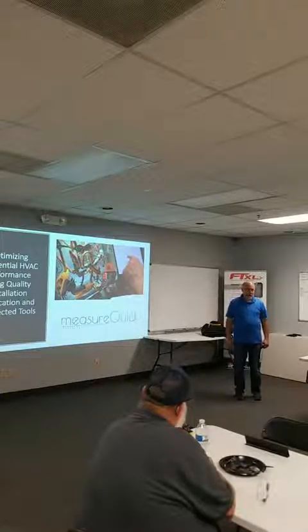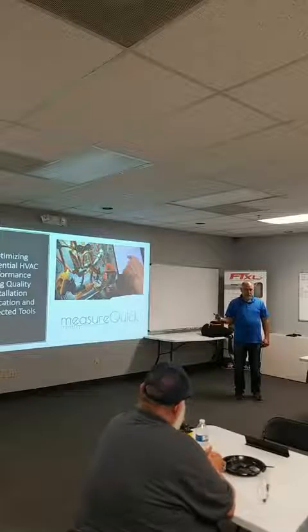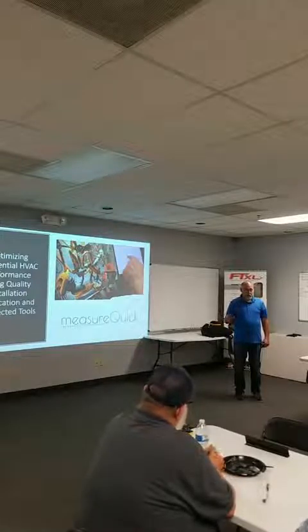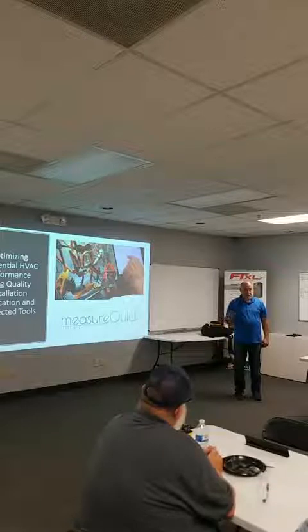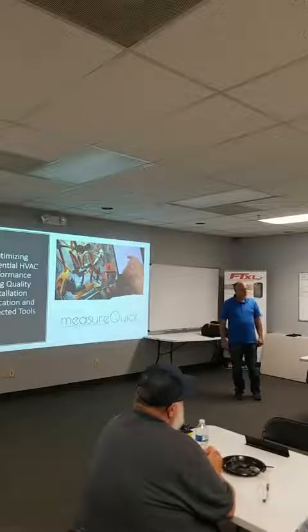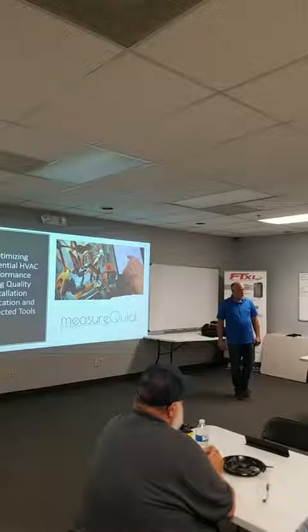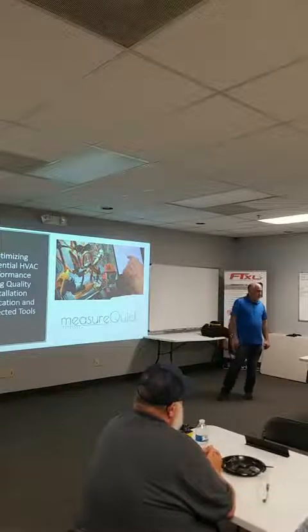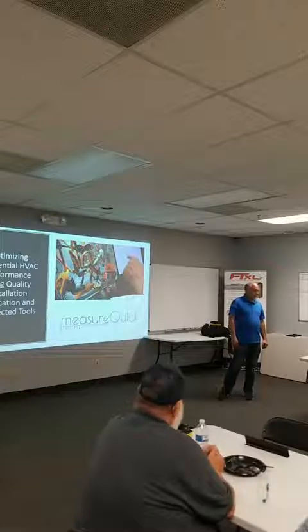That was the first piece of understanding Measurequick. Back when I started teaching school, I started teaching the kids design temperature differences, and then I realized that every single measurement we take can be back calculated to what it should be based on the load conditions. Now, do you have a humidity sensor? Because if you have very high humidity, your TD on your supply and return will be lower because of the load. Yes, and we recalculate that continuously.